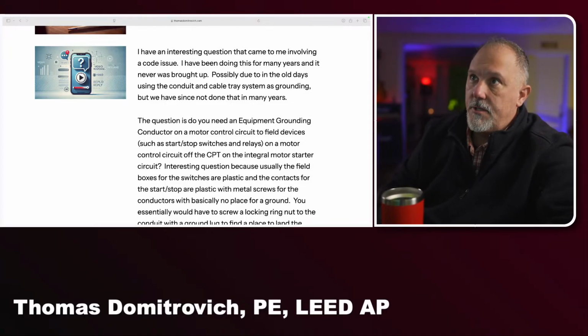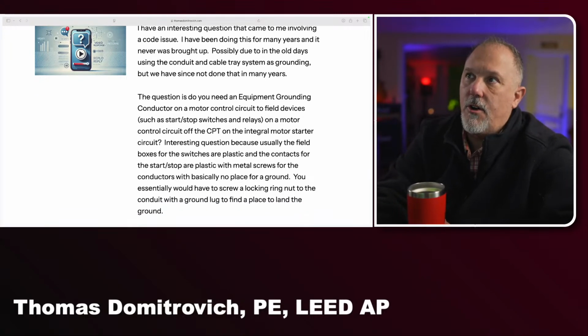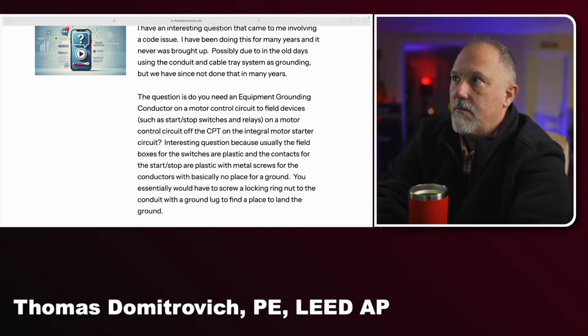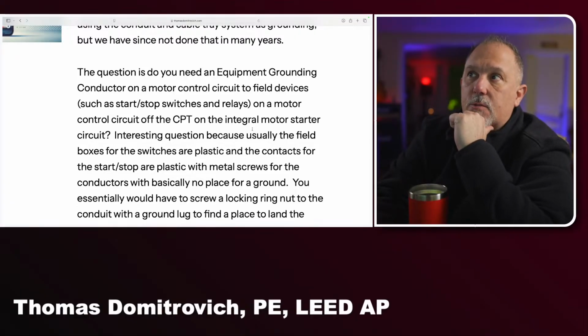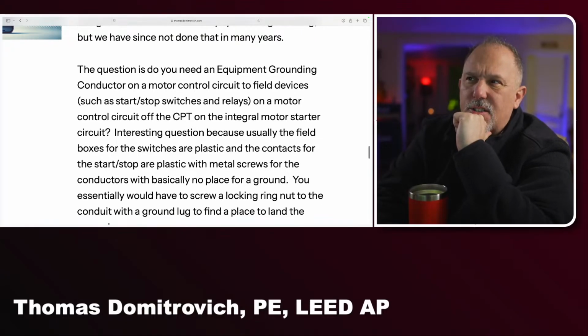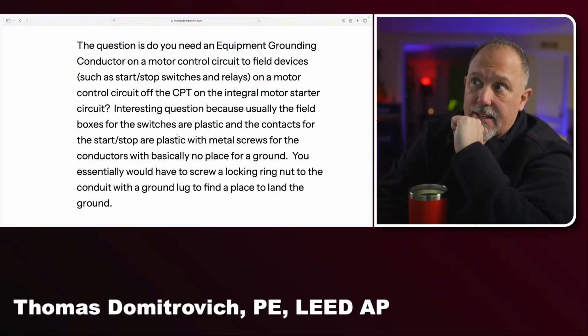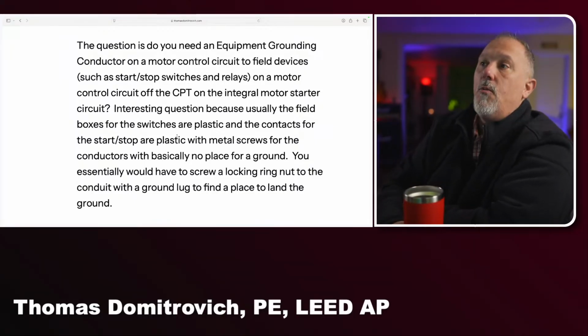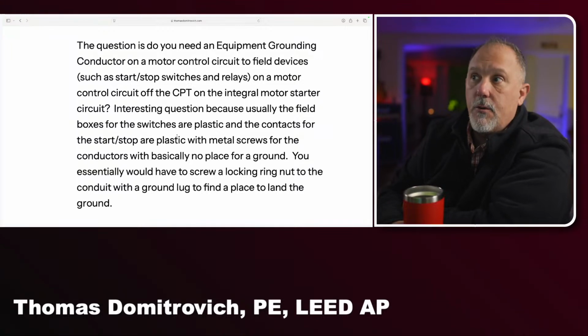I've been doing this for many years, and it was never brought up, possibly due to the old days of using the conduit and cable tray systems as grounding. But we have since not done that in many years. The question is, do you need an equipment grounding conductor on a motor control circuit to field devices such as start-stop switches and relays on a motor control circuit off the control power transformer on the integral motor starter circuit? Interesting question, because usually the field boxes for the switches are plastic and the contacts for the start-stop are plastic with metal screws for the conductors with basically no place for a ground. You essentially would have to screw a locking ring nut to the conduit with a ground lug to find a place to land the ground.